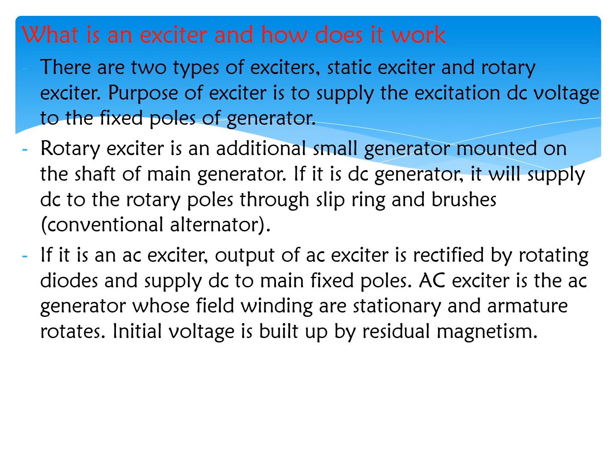What is an exciter and how does it work? There are two types of exciters, static exciter and rotary exciter. Purpose of exciter is to supply the excitation DC voltage to the fixed pole of the generator. Rotary exciter is an additional small generator mounted on the shaft of the main generator. If it is a DC generator, it will supply the DC supply to the rotary poles through the slip ring and the brushes. If it is an AC exciter, output of the AC exciter is rectified by the rotating diodes and supplies DC to the main fixed poles.